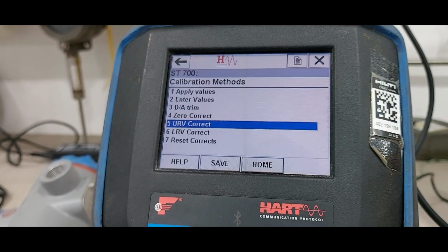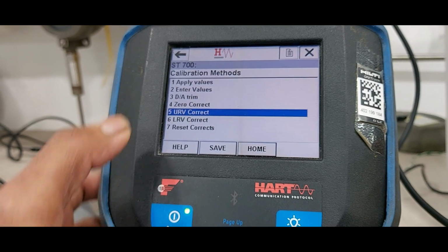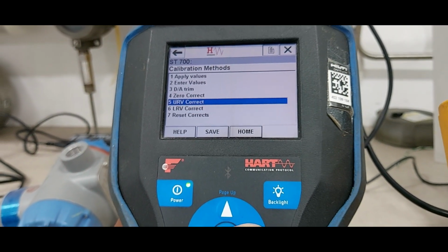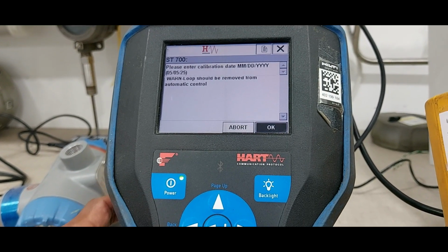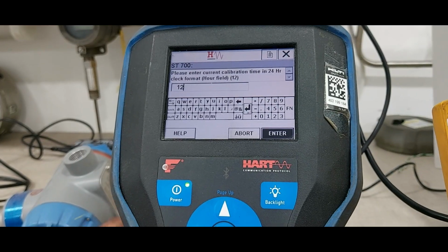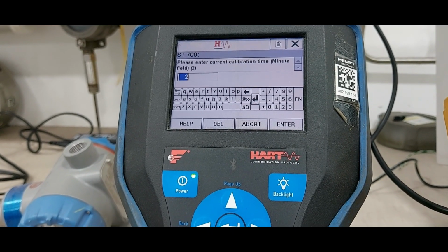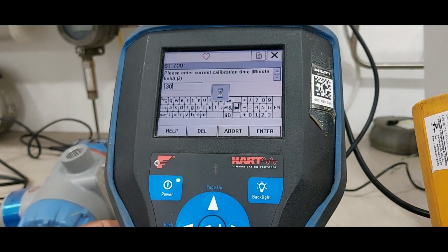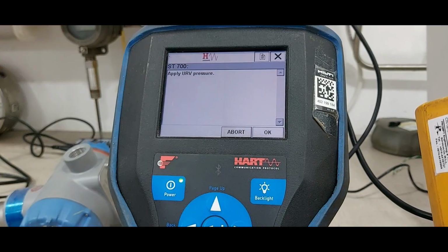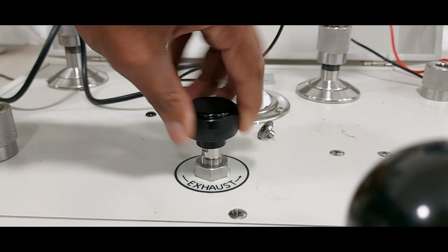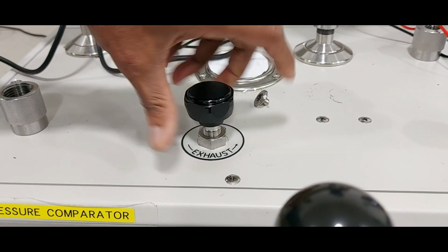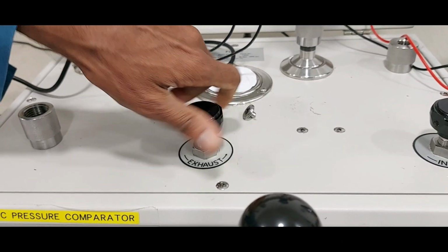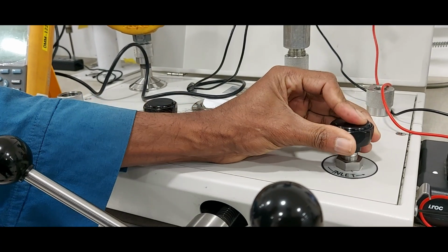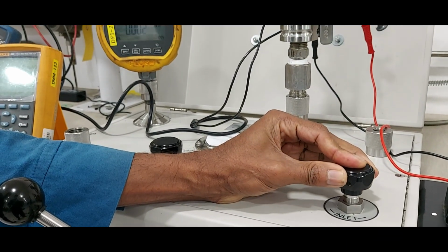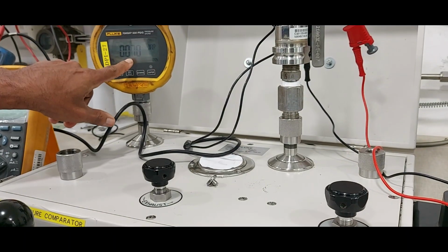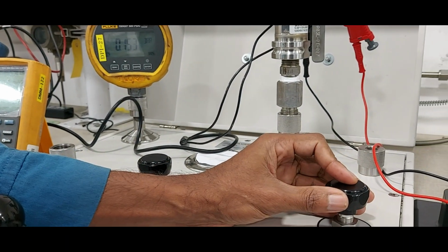Next, we are doing the span trim, upper range value trim. We are selecting number 5, upper URV corrected. Next, OK. Date, that's OK, fine. OK. 30, OK. Apply the URV pressure. Close the vent valve. Slowly open the inlet valve. Now pressure will be increased. Slowly open.